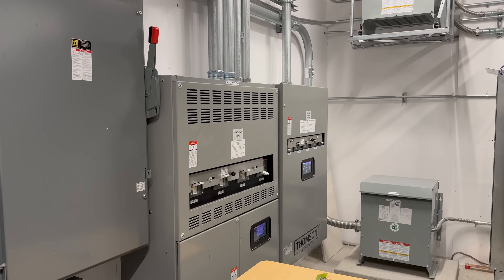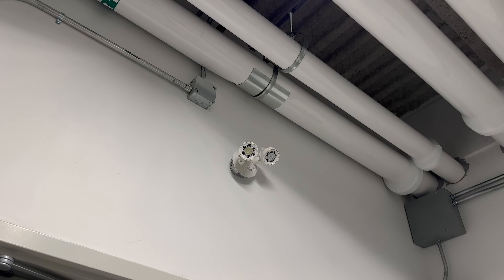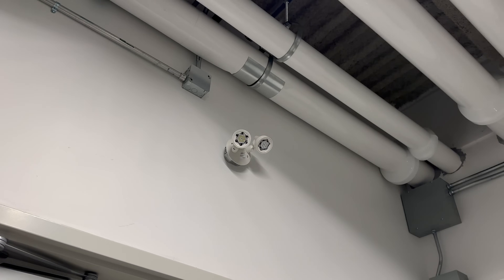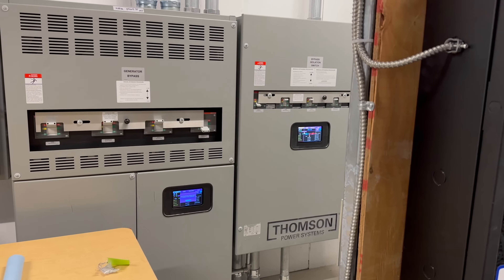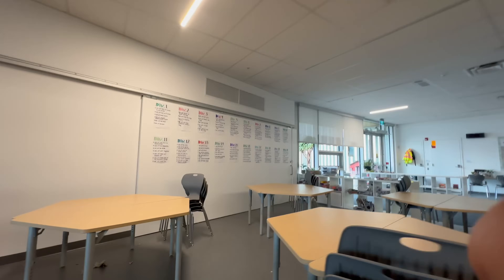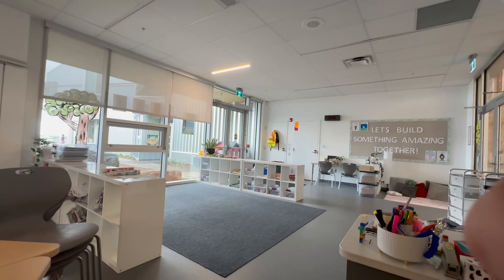The elevators are also kept on emergency power at both of these schools, and there's battery backup emergency lights in some areas, as well as UPSes on the data to keep it going in between the time of the generator starting. Two lights on the library on emergency and then the exit sign. Maybe the library is upstairs — never mind. So basically one side of the hallway is kept illuminated.